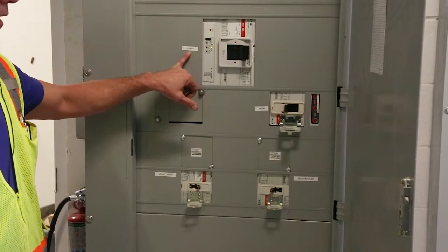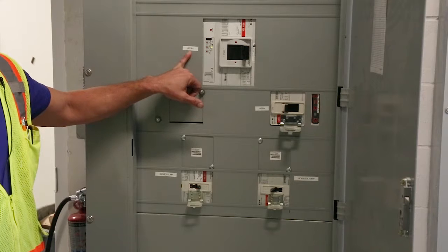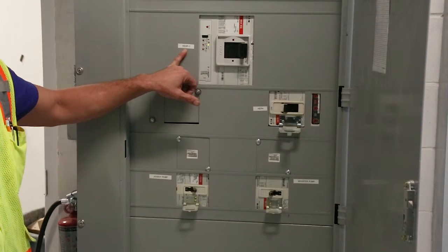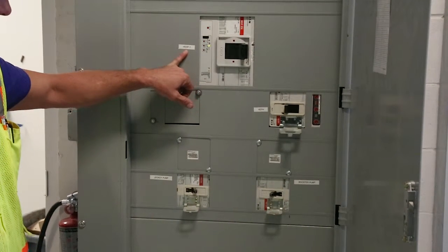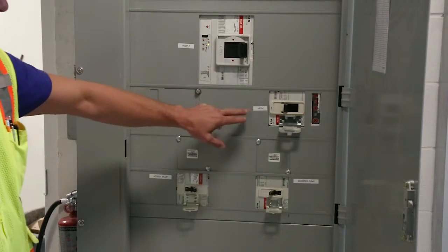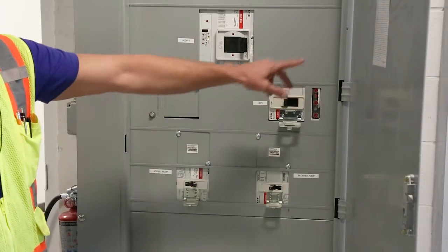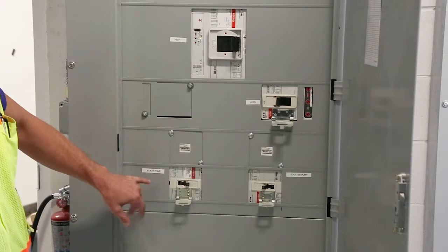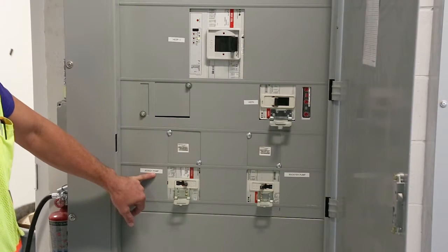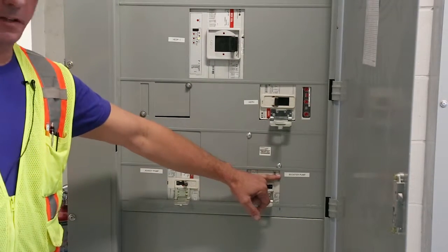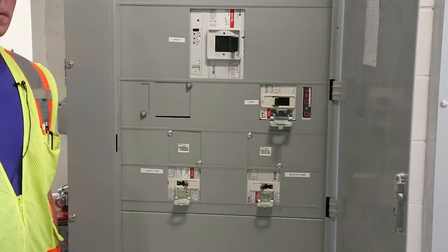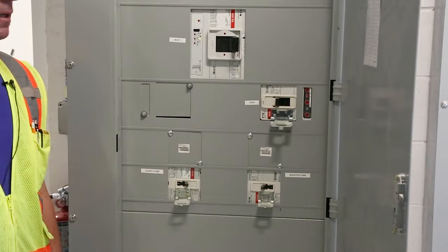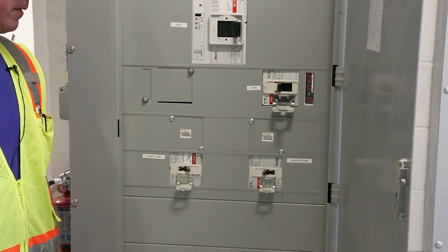This does all your elevator equipment rooms and anything to do with emergency power and elevators in the North Tower. This breaker feeds HEPH, which is right next to this panel. This breaker feeds your jockey pump, and this breaker feeds your booster pump. Okay, this is a 277/480 volt panel.